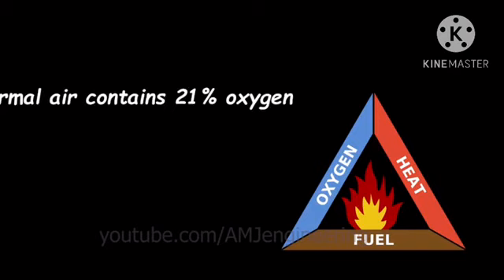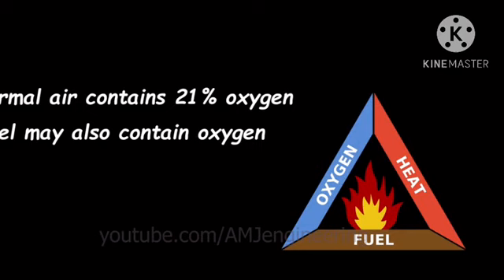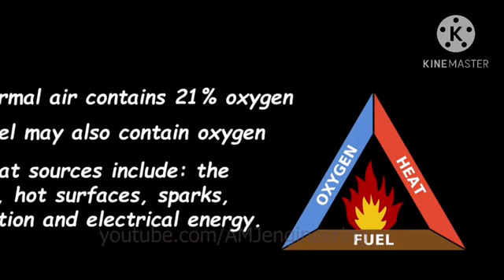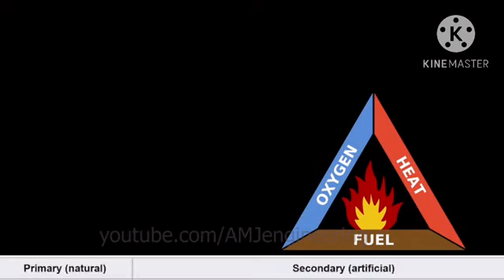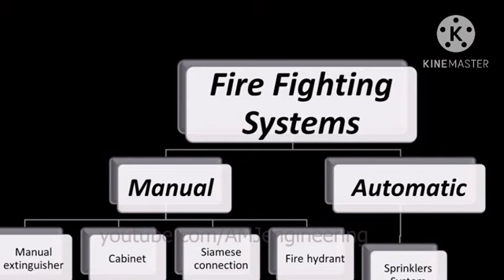Normal air contains 21% oxygen. Fuel may also contain oxygen. Heat sources include the sun, hot surfaces, sparks, friction, and electrical energy. Fuel sources can be a solid, liquid, or gas. Firefighting systems are classified as either manual or automatic. Manual firefighting systems include extinguishers, fire cabinets, Siamese connection, and fire hydrants. These require the physical intervention of manpower to fight the fire.